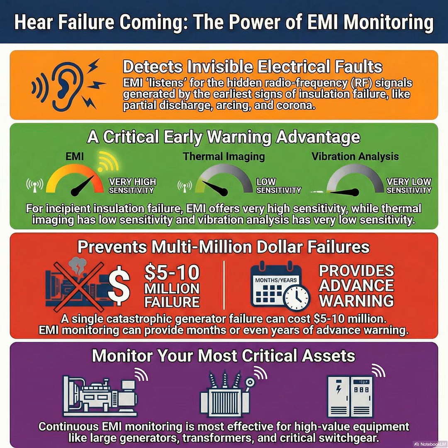It absolutely is. Traditional methods only confirm damage when it's already pretty far along. For these high-value assets, generators, large transformers, a single unplanned failure can easily cost 5 to 10 million dollars in equipment and downtime. Detecting that fault early turns a 10-day catastrophic outage into a planned, maybe 4-hour repair. It's a huge difference, and leveraging all that high-frequency noise to find the pattern requires some pretty advanced data solutions.